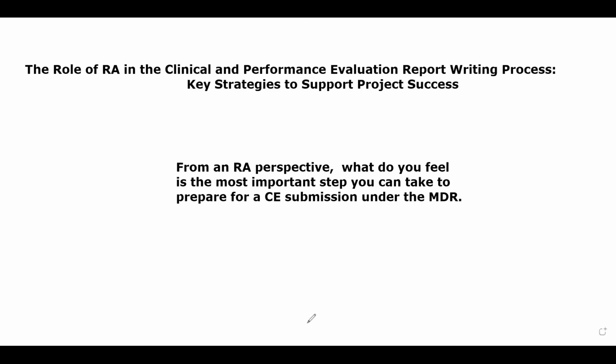will. Remember, we get a lot of questions about well-established technology. So the writer is going to need to know whether we need to deploy MDCG 2020-6, which relates to well-established technology, or does Article 61(10) come into play, because there are issues perhaps with your clinical data and claims and patient benefits. So the regulatory strategy, route of conformity decision must take into account data sufficiency, equivalence questions, all of that. So I would say that's the most important and most careful decision to make.